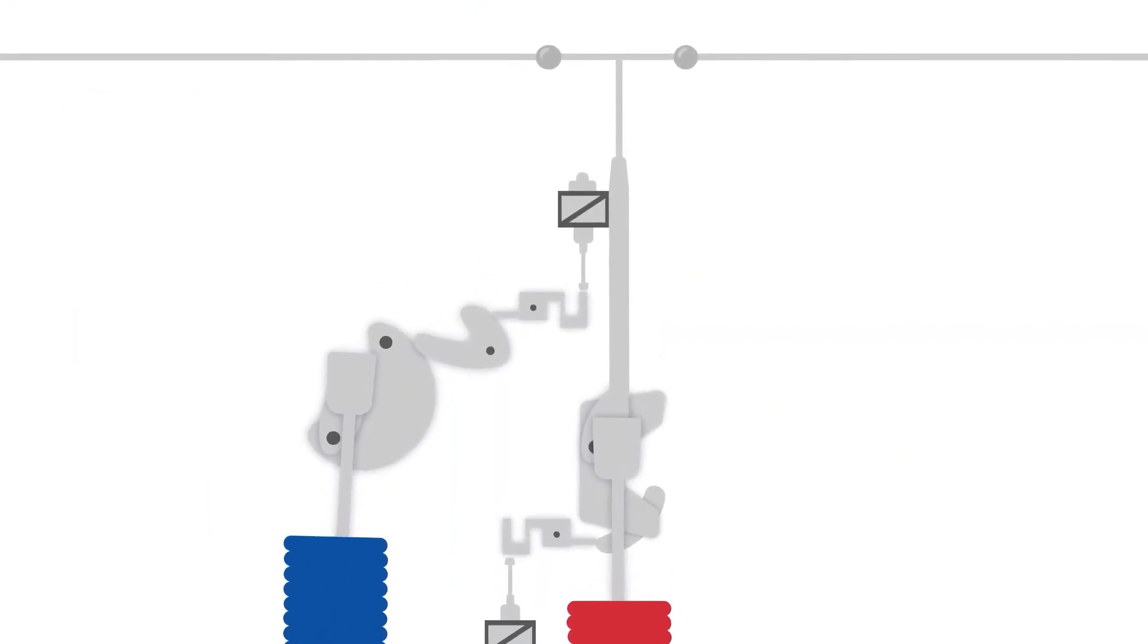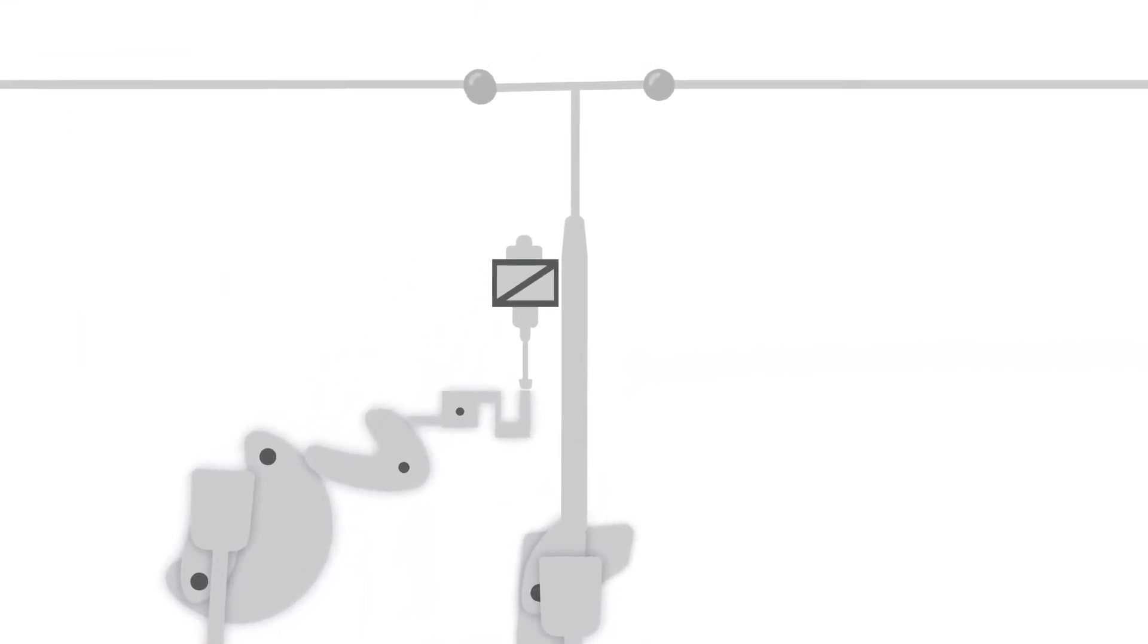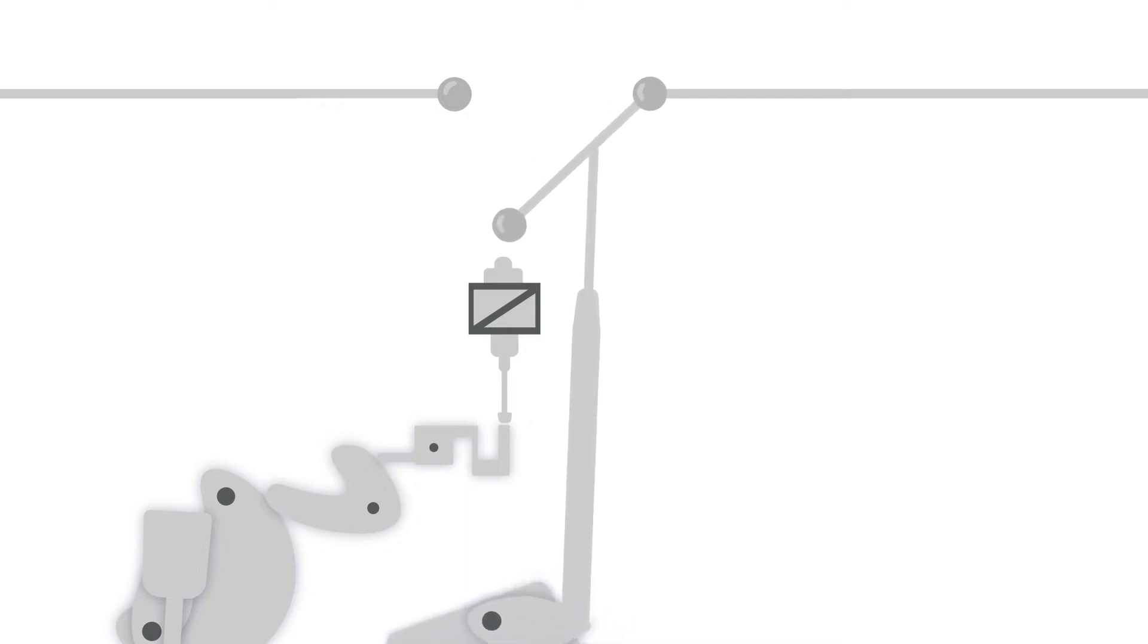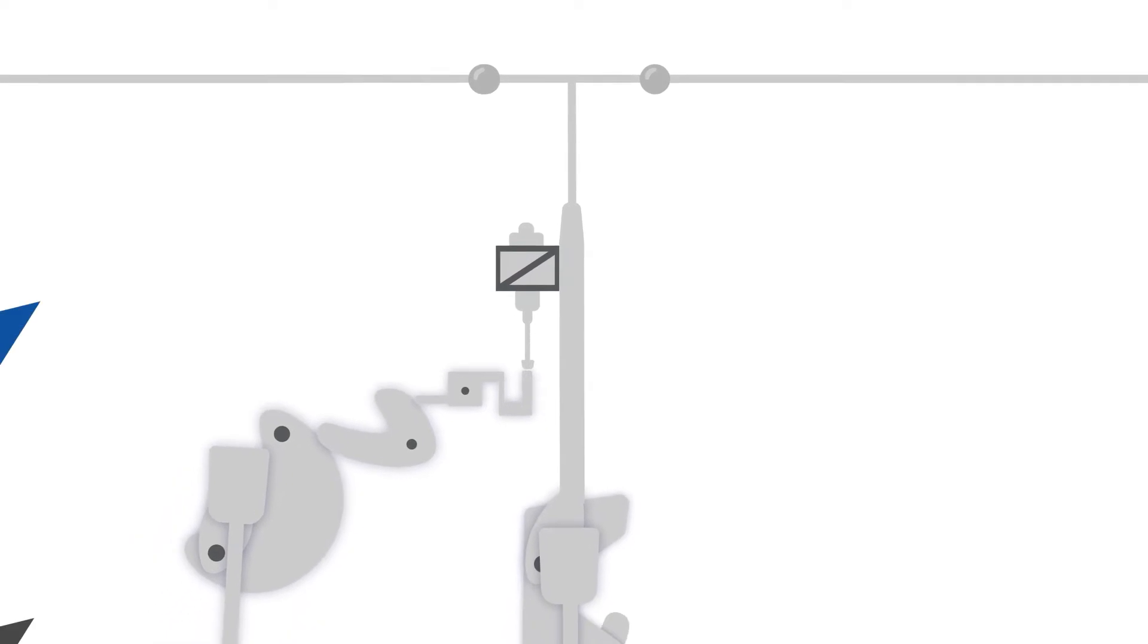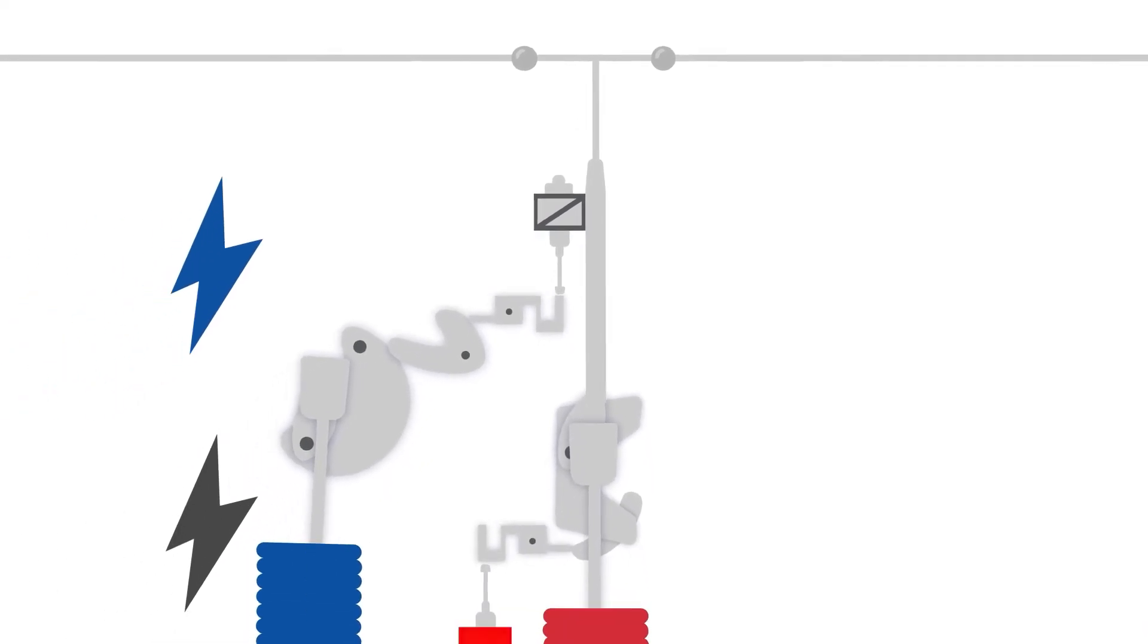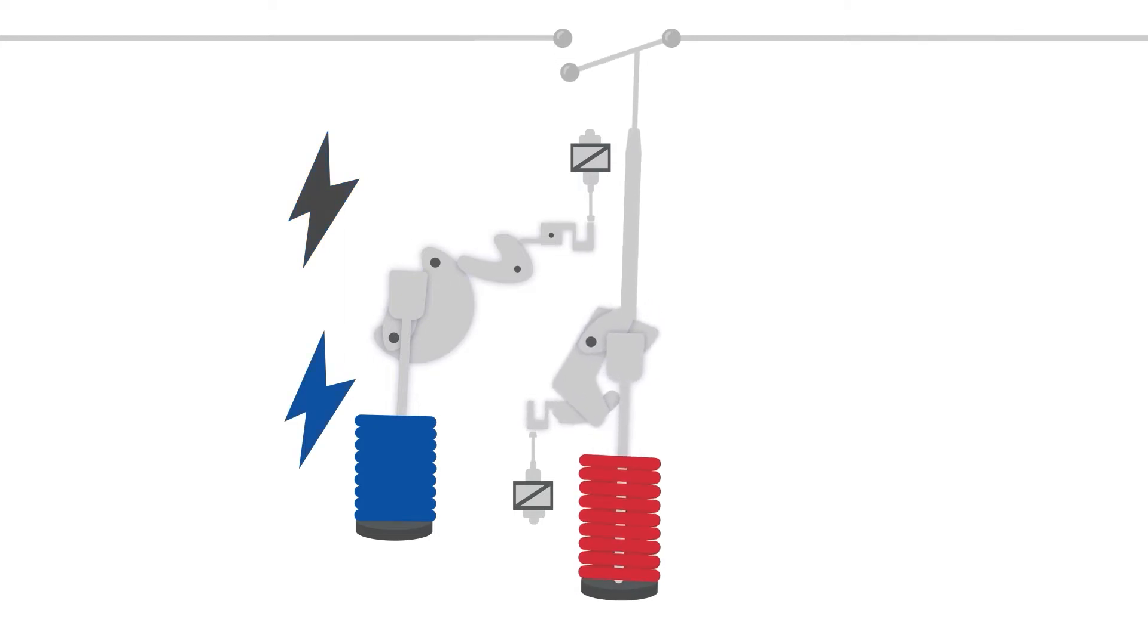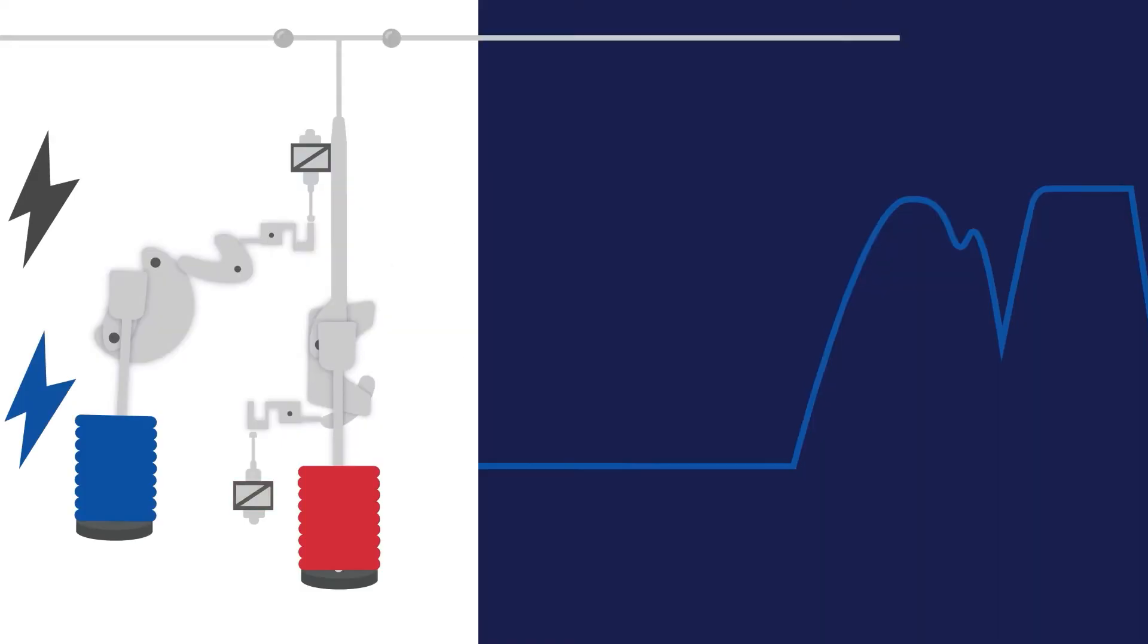While the trip coil is in the maximum current state, the main cam on the mechanism has started to move and, through attachments to linkage, is beginning to open the switchgear's main contacts. As the mechanism moves from the closed to open position, linkage attached to the auxiliary contacts opens the 52A switch and closes the 52B switch to prepare the switchgear for a closed operation.